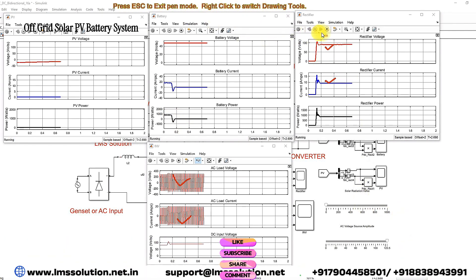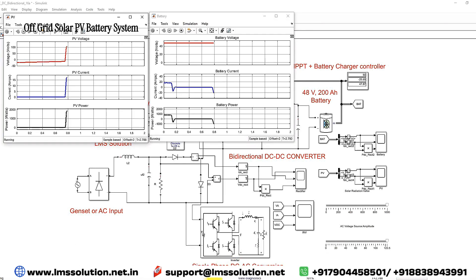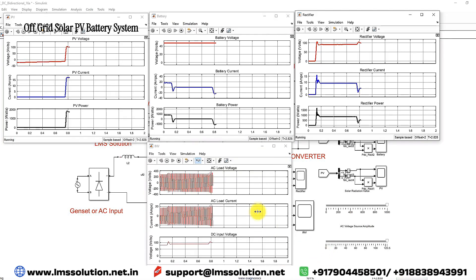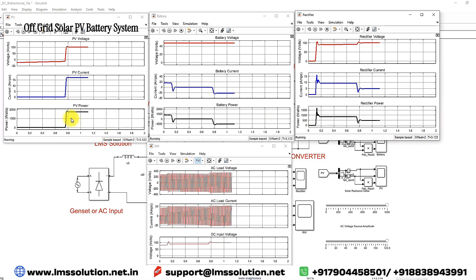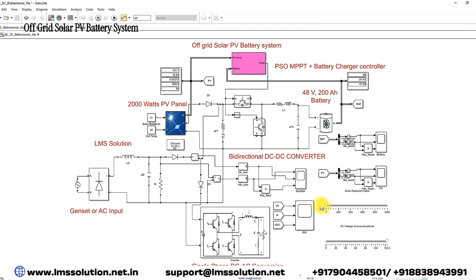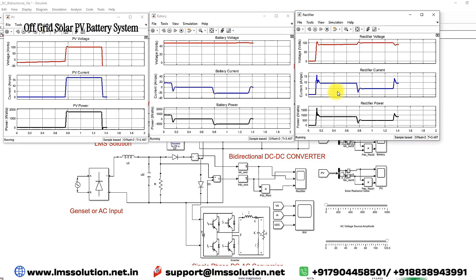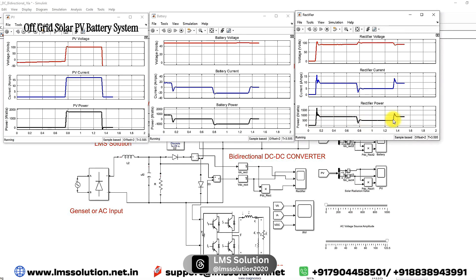Now I am going to increase the irradiation. Because of increasing irradiation, the PV power increases. The excess power will charge the battery as well as supply the AC load. The power sharing of the generator set decreases to around 500 watts because the PV is generating some power. If the PV power is decreased again, the battery goes to idle condition and we get power from the generator set to supply the AC load.